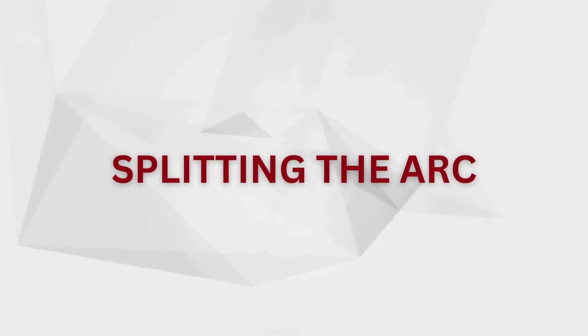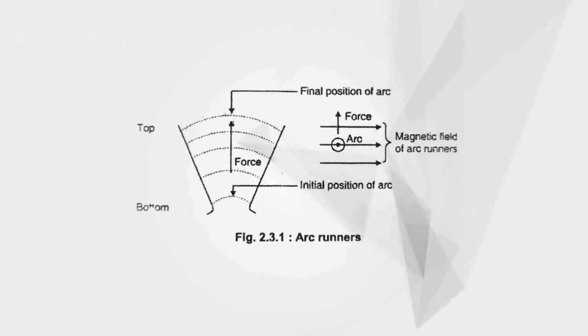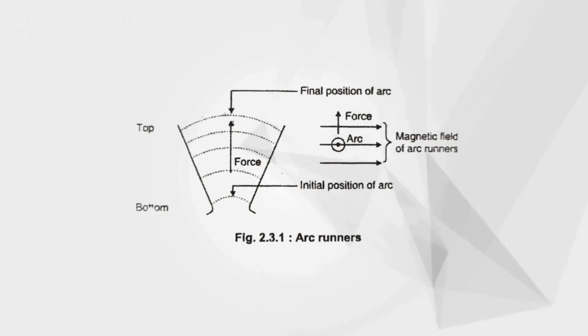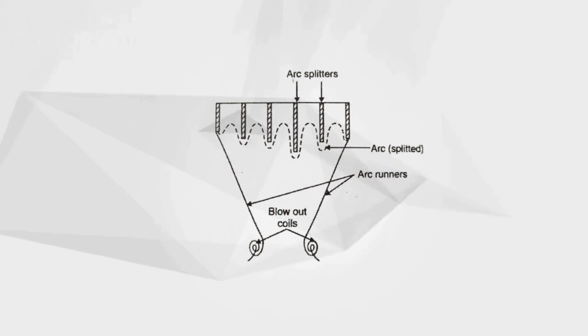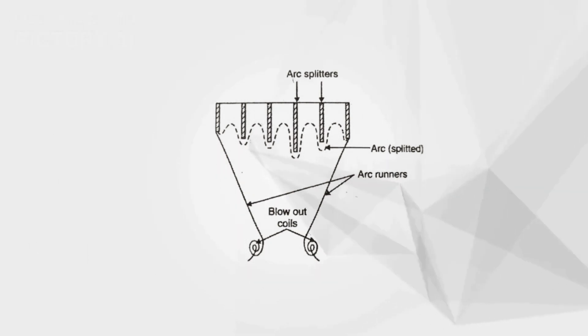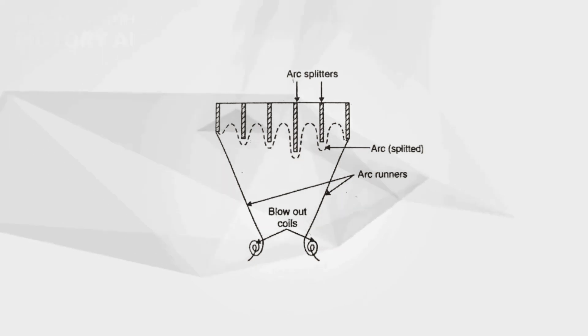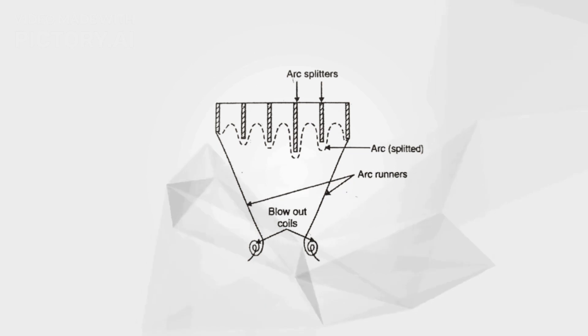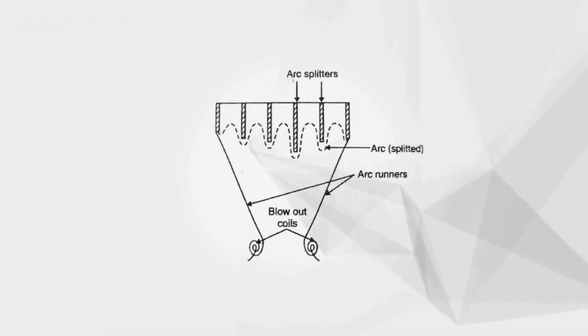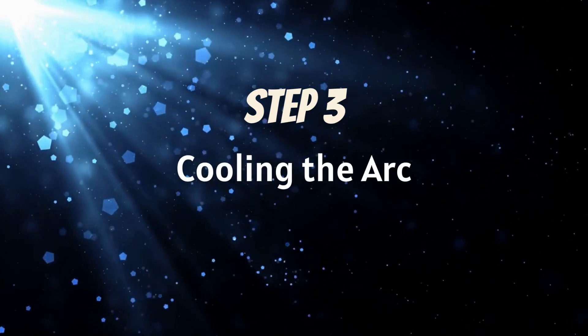Step 2 — Splitting the arc: The arc is elongated by means of arc runners, and its length can be further increased by splitting the arc. Arc splitters are used for this purpose. The arc splitters are made up of resin-bonded fiberglass and are located at the top of arc runners, placed in a perpendicular direction. The blowout coils produce a strong magnetic field that pushes the arc toward the arc splitters.